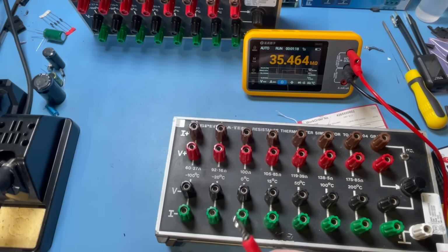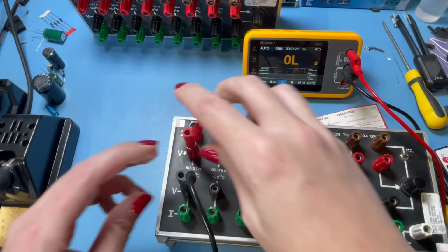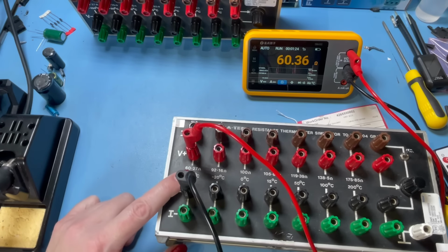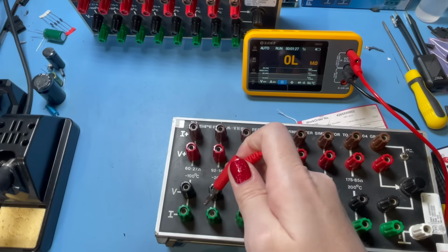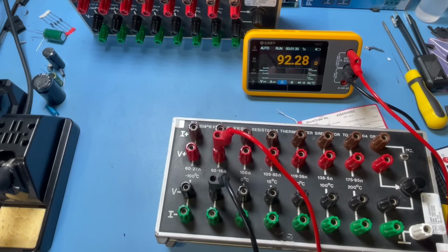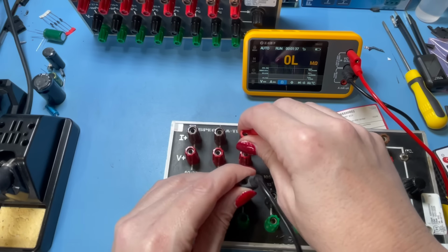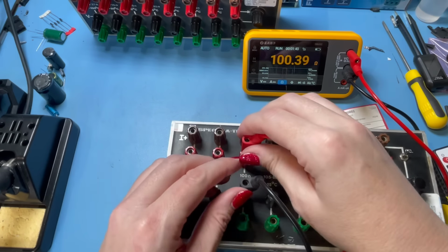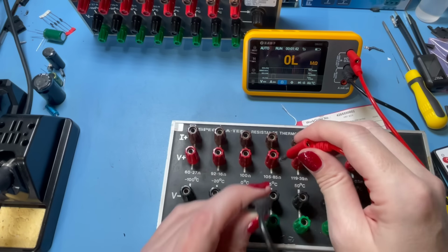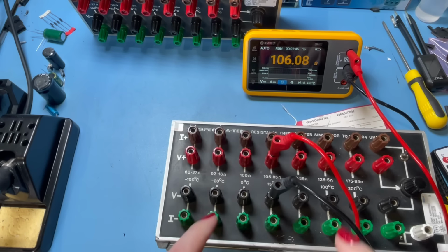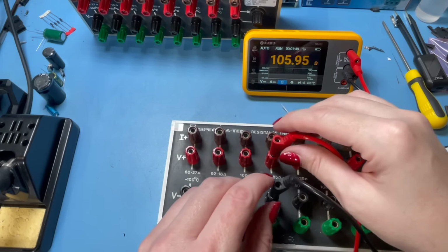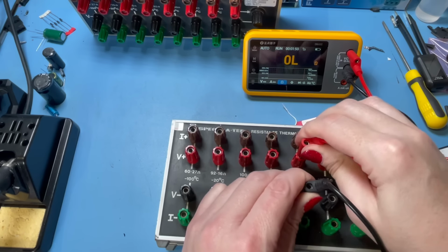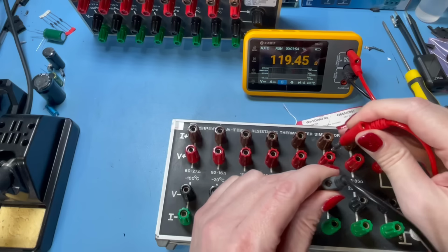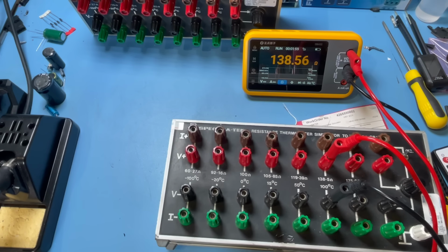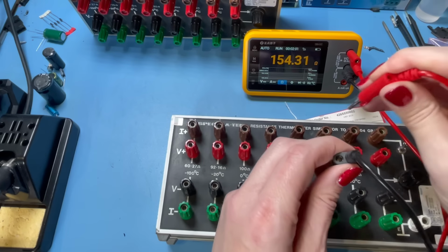Alright, so just out of interest then, let's have a play. 60.27 ohms. Oh, alright, 92.16. Either this box is excellent or this meter is pretty good, or a bit of both. 100 ohms. 105.85. These are very specific, and these are specific to testing these kind of probes. 119.39. It's pretty good. 138.5. Oh, almost spot on.